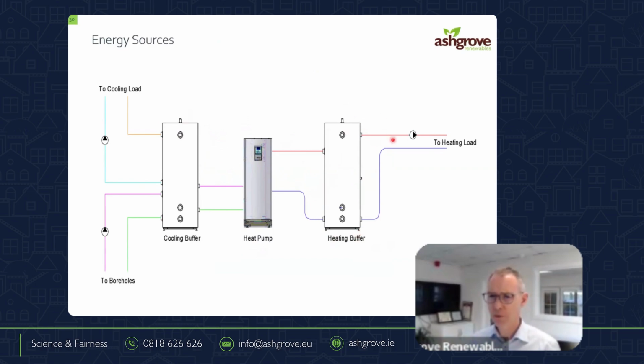I can use it to create hot water. I can send it to radiators. I can send it to underfloor heating. I can send it to fan coils or whatever it is in a commercial building. But over here, we have any amount of possibilities. But when I'm taking energy out of it, I have to put energy back into it so I can take it out again in an hour. Sometimes we use that from a cooling load in a building, or it might be an abattoir or a process through the refrigeration. We're cooling, right? And then if for any reason I'm taking out 100 kilowatts on the hot side, and I'm only putting in 70 kilowatts on the cooling side, I need to make up the shortfall through the boreholes.